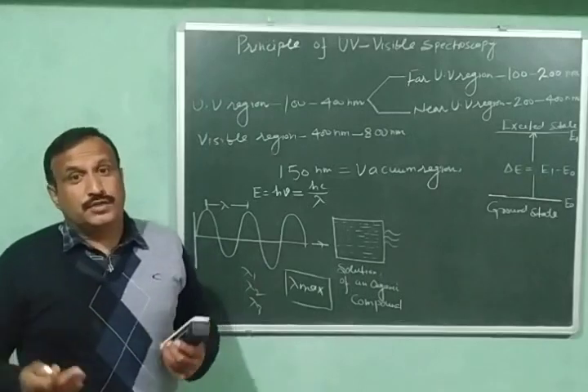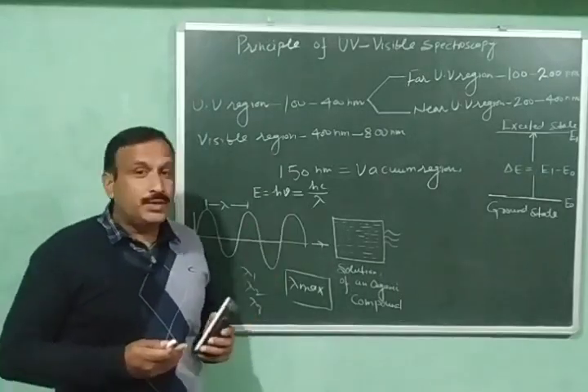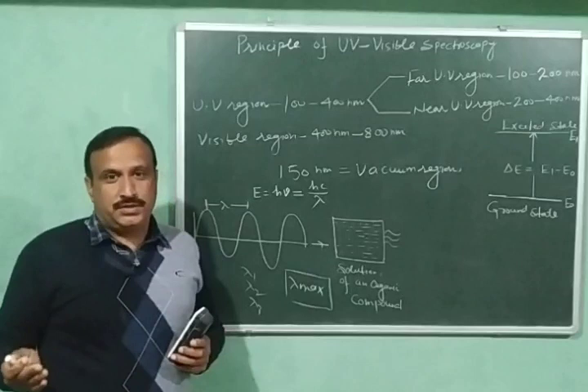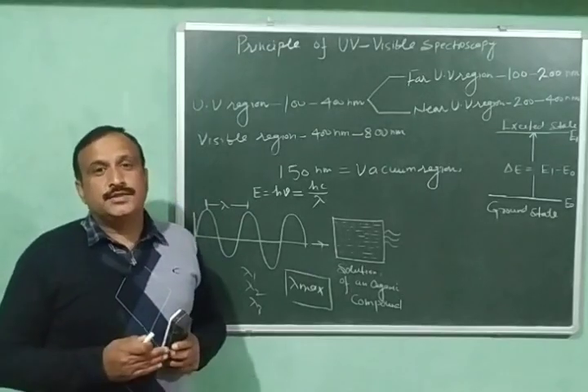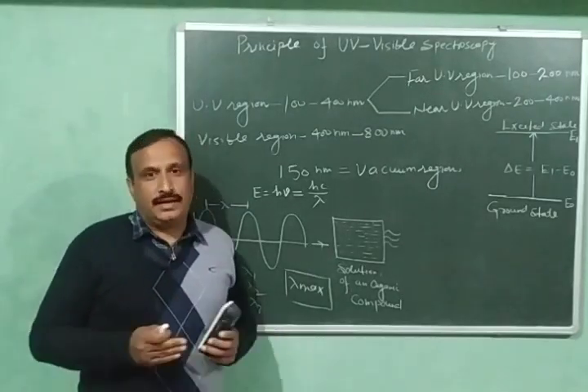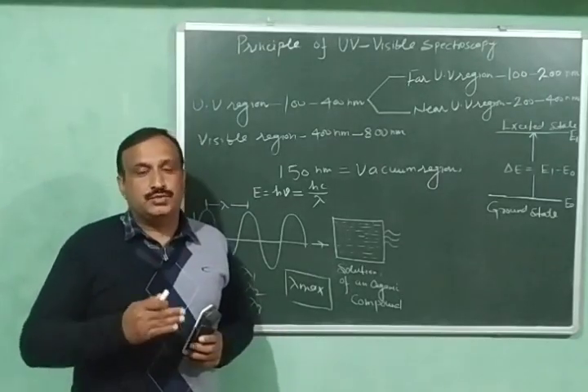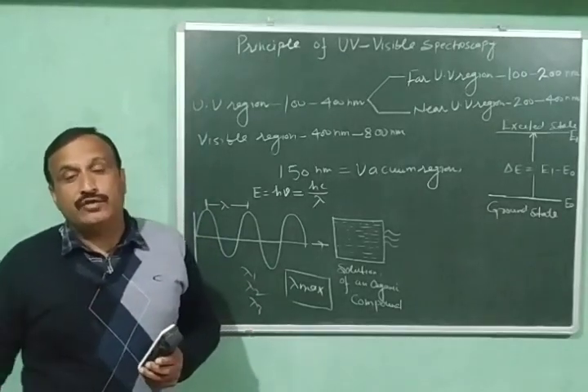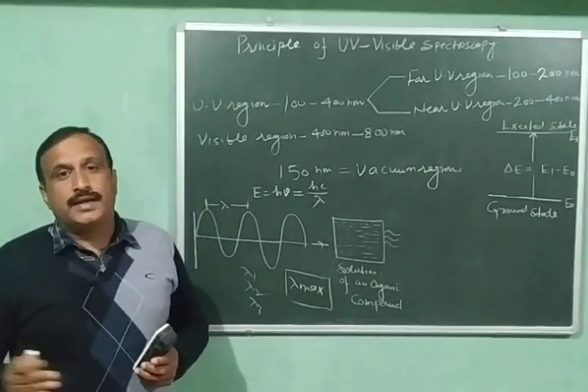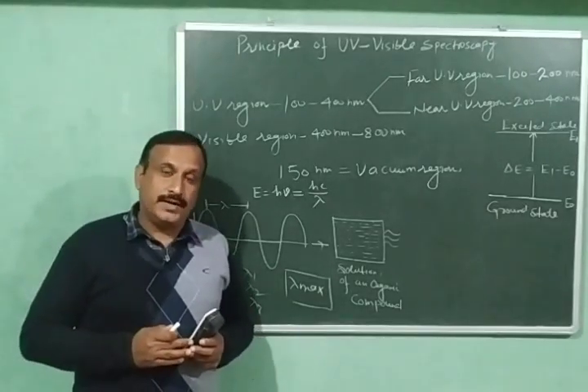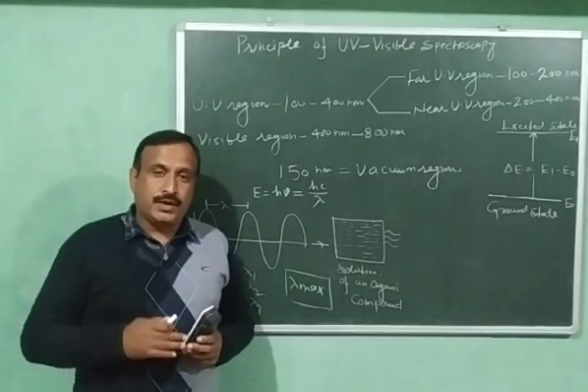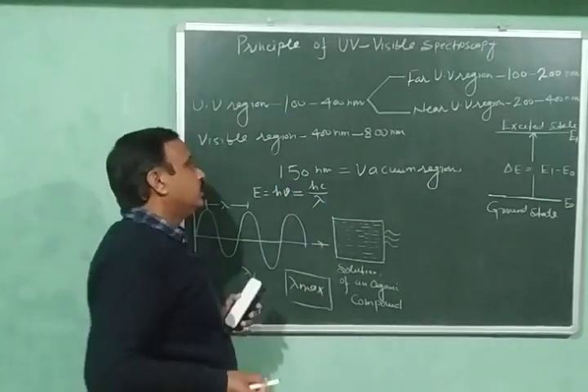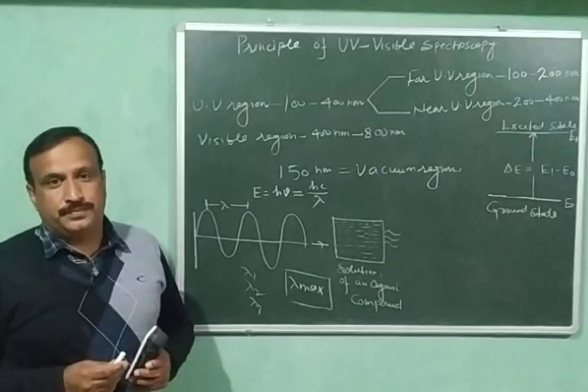So for measurements below 150nm we need an evacuated instrument — that is, the instrument must be free from any gas, there must be complete vacuum. Some vacuum techniques are also required in this case. That is why the region below 150nm is called the vacuum region.